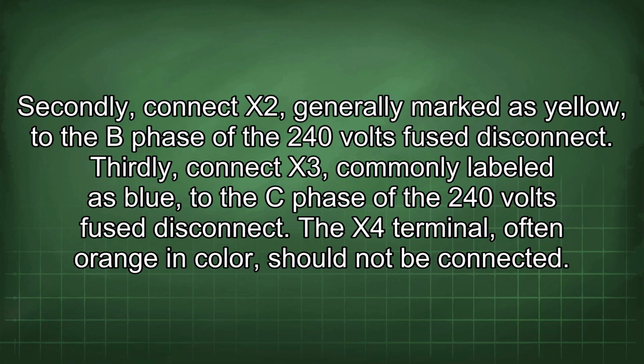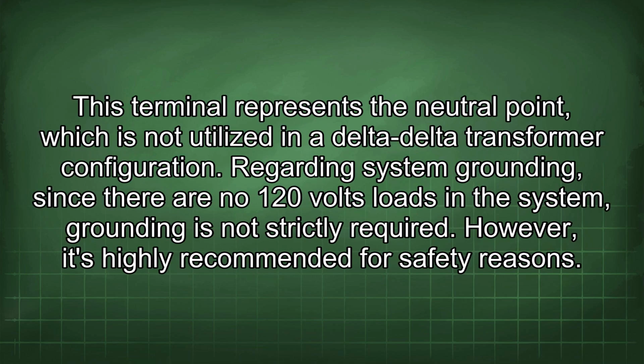The X4 terminal, often orange in color, should not be connected. This terminal represents the neutral point, which is not utilized in a delta-delta transformer configuration. Regarding system grounding, since there are no 120 volts loads in the system, grounding is not strictly required. However, it's highly recommended for safety reasons.